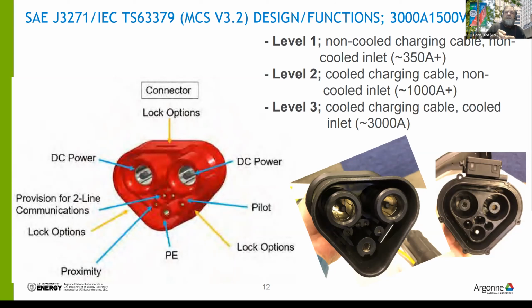You can see the yellow arrow that says lock options. So there are slots in the housing for the big locking bars, and you can see on the far right, there's a little box that's a servo motor that pushes a pin and locks the 2 sections together, such that when the connector is mated, it can't be unmated until it's unpowered and cool.